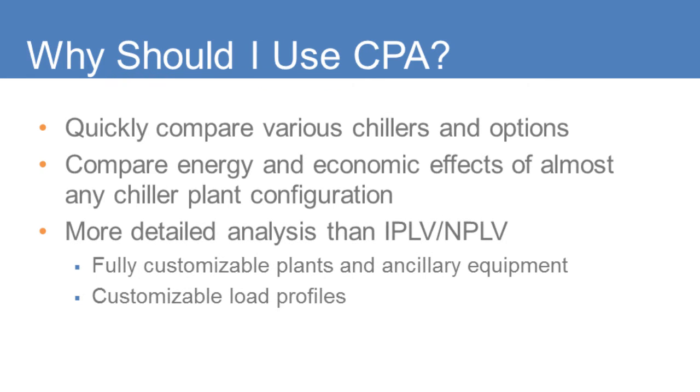Chiller Plant Analyzer will allow you to evaluate the economic impact and life cycle cost payback of almost any chiller plant configuration. The life cycle cost of a chiller is much more significant than its initial cost, so it is important to evaluate this when specifying and purchasing equipment, especially considering that chillers will last an average of 20 to 25 years. Additionally, some people use IPLV or NPLV efficiency values to quickly calculate a life cycle cost for a chiller. Chiller Plant Analyzer will give you much more accurate energy and economic information compared to using IPLV or NPLV efficiencies for life cycle cost estimates.